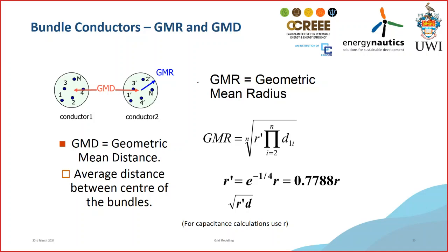I also have to get what is called the geometric mean radius and geometric mean distance. The geometric mean radius is really what is the equivalent radius of all these conductors which are in this bundle. What is the equivalent radius? And the geometric mean distance is, once we treat this bundle as an equivalent conductor, the actual geometric mean distance between these two conductors as strand it on the tower that we have shown before.